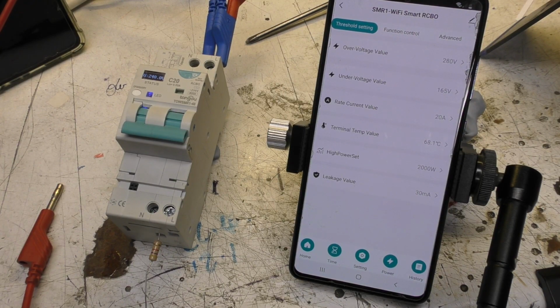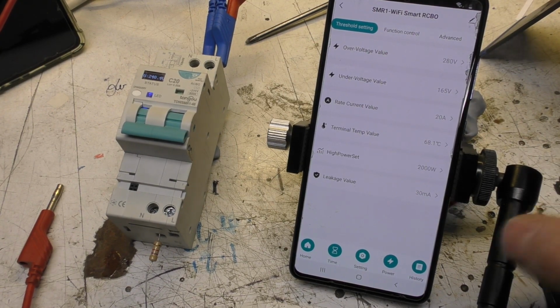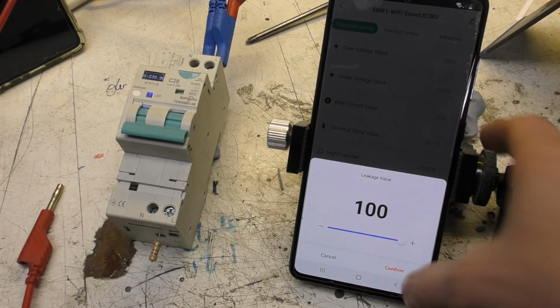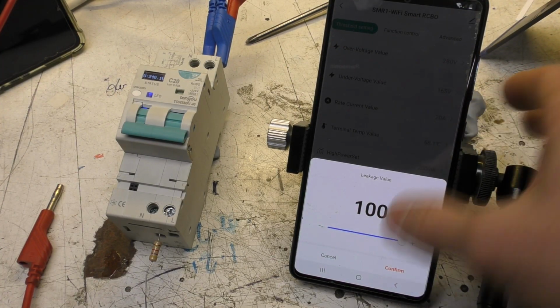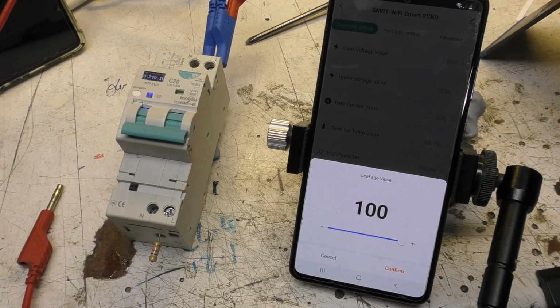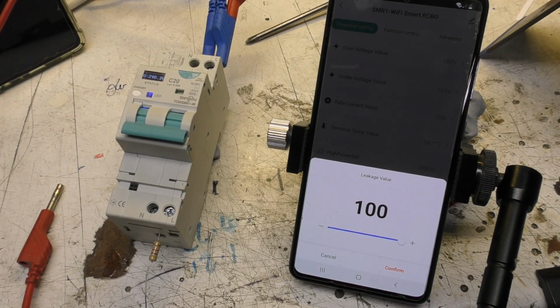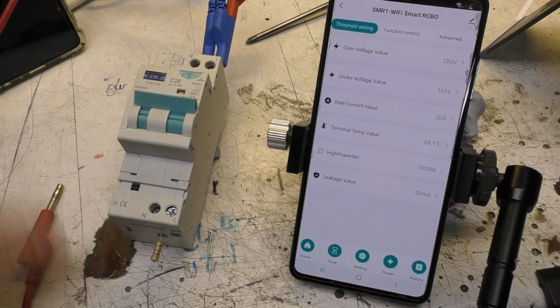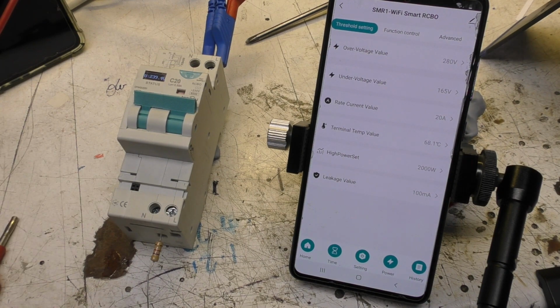I haven't got a simple way of doing that, but it does trip. So let's change the leakage value. The highest it will allow is 100 milliamps, which is a standard for some larger breakers. For example, you're protecting certain types of installations where you might have 30 milliamp breakers downstream, so that it trips the downstream one first. Turn it on, not tripping.